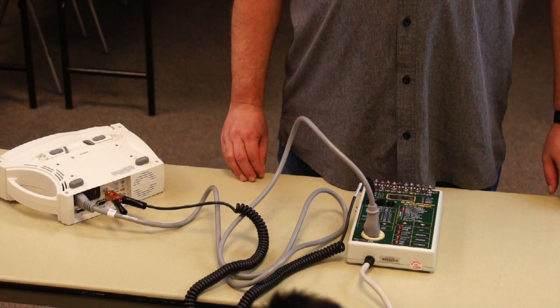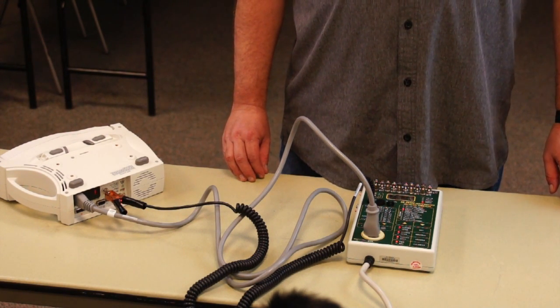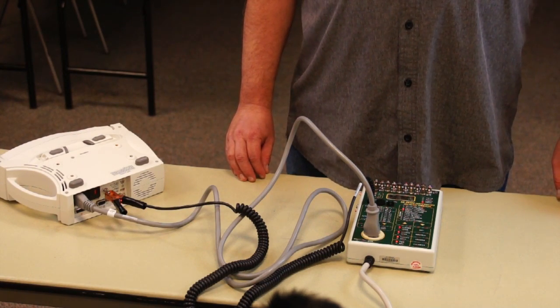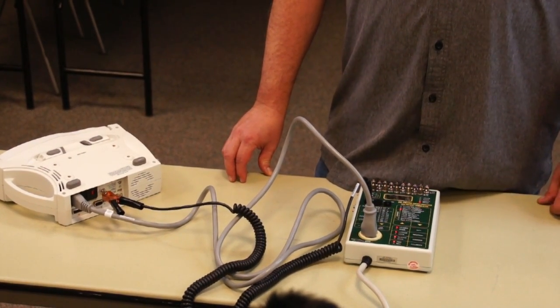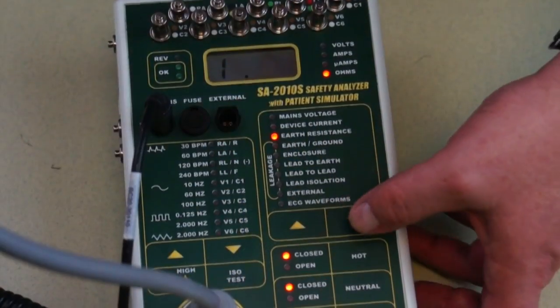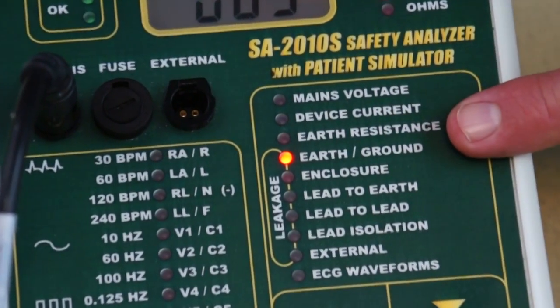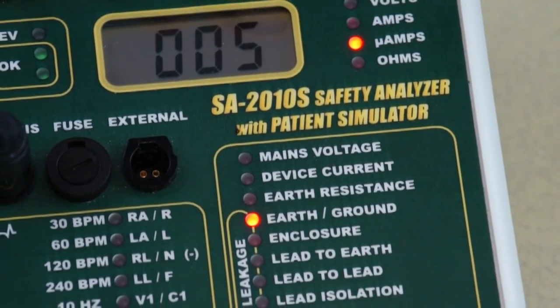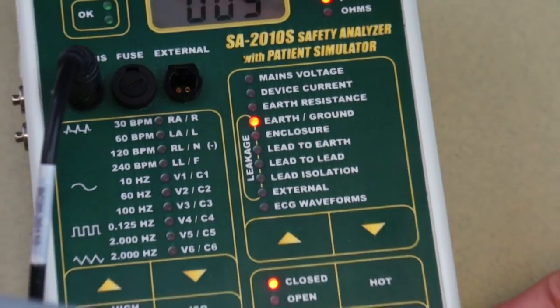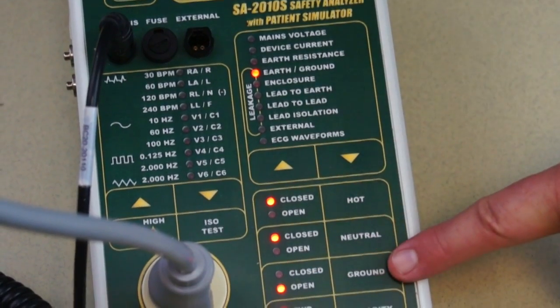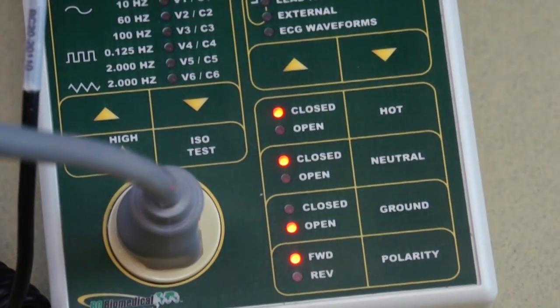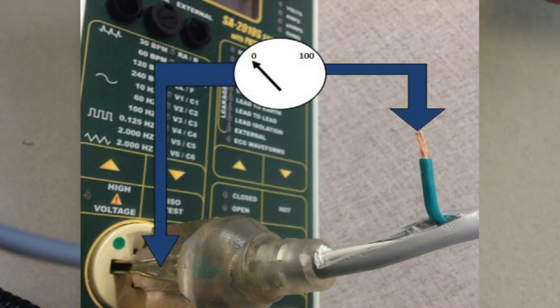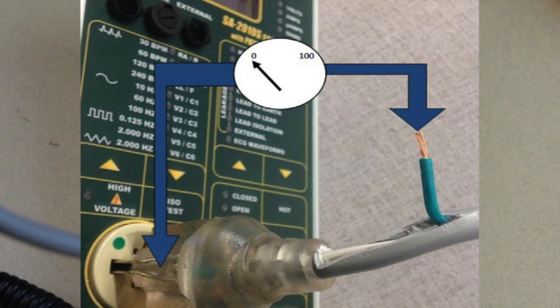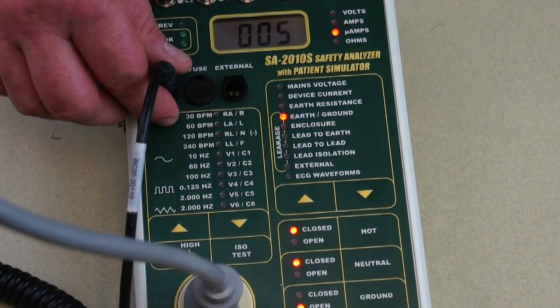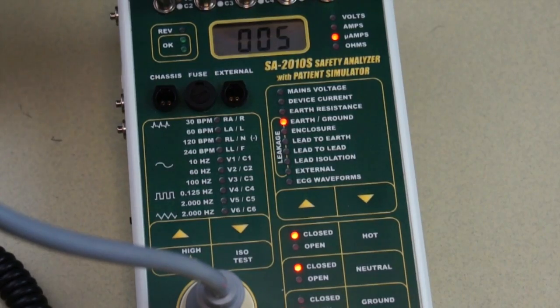The next test we will perform is the current leakage test. There's a couple of ways to do this. The first way I will demonstrate is by setting the mode to earth ground. Notice by default, the test receptacle is showing that the ground wire is open. Internally, the leakage current is measured through the safety ground line from the device. This is the current that would normally be flowing through the ground wire. The Kelvin lead is not necessary for this test.